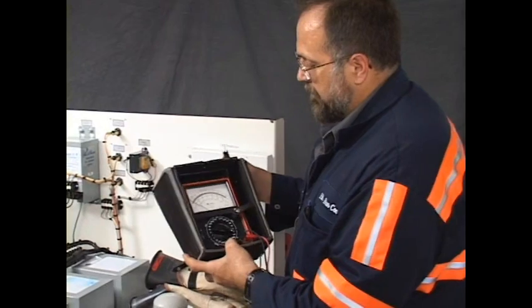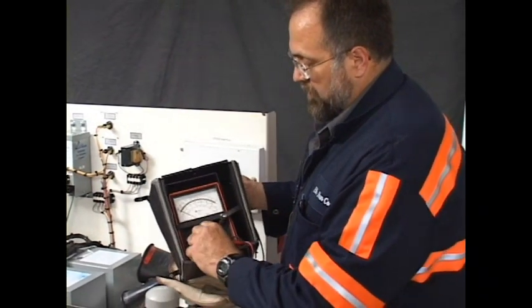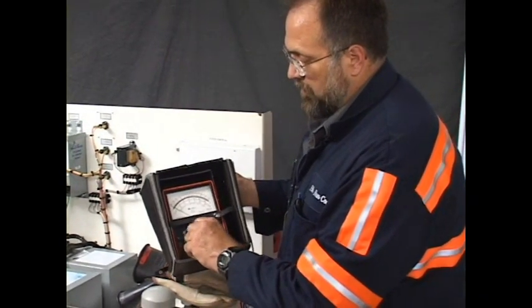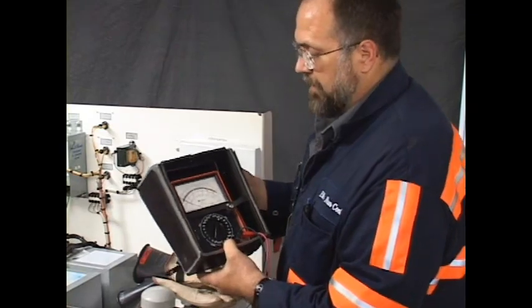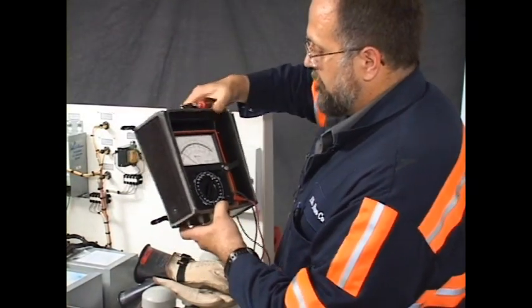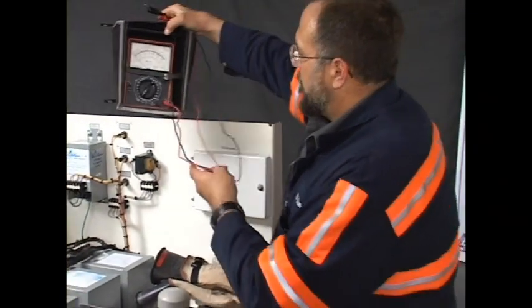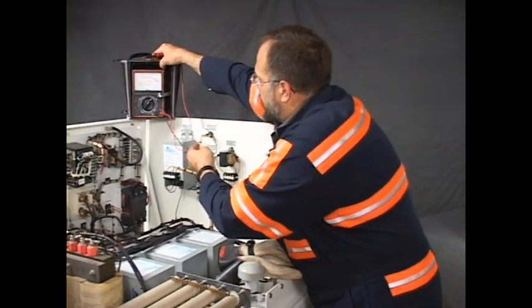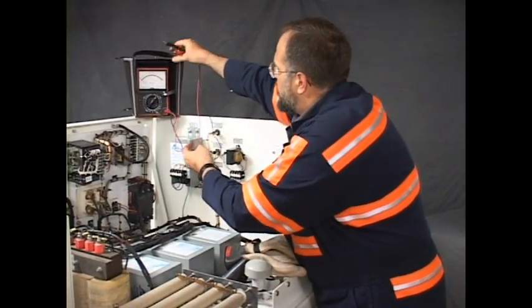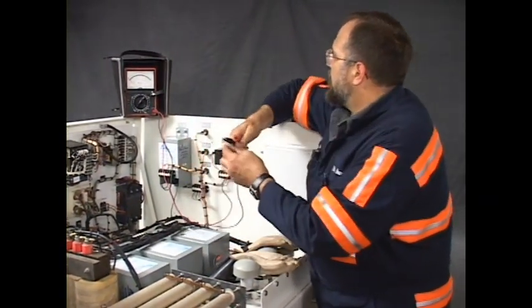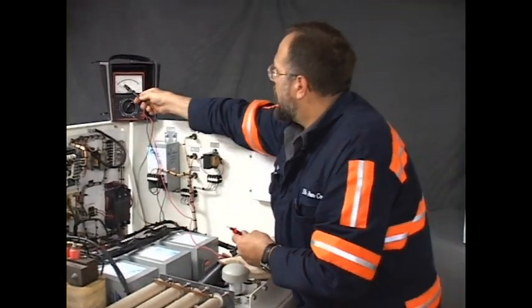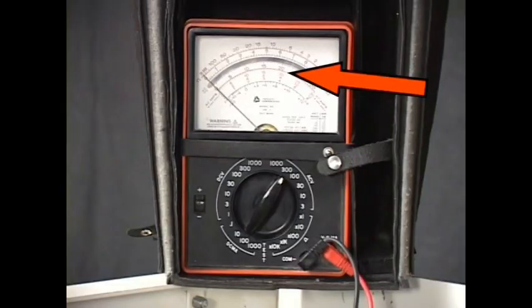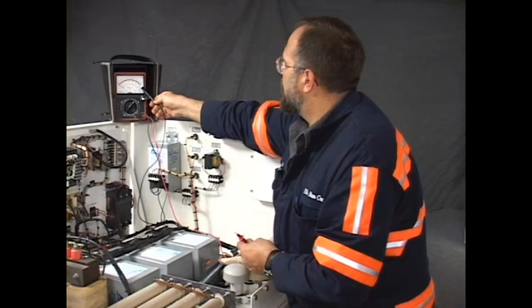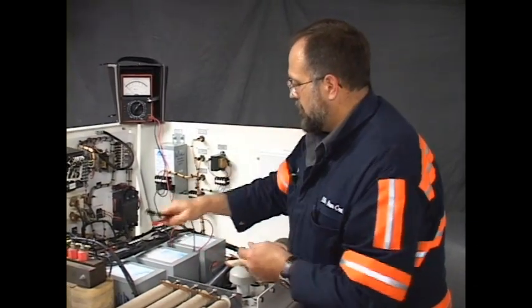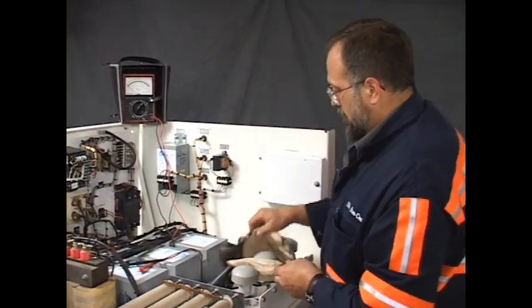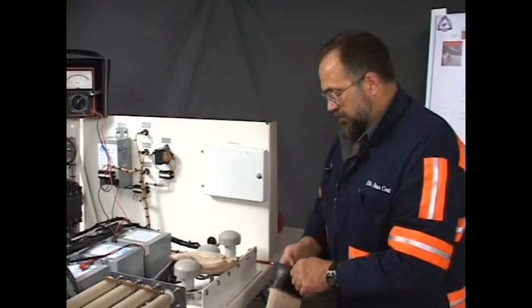I'm going to change that to read AC voltage. And I'm going to choose a scale higher than what I anticipate finding in voltage. And I've done that. We anticipate having a 120 volt control circuit. I've chosen a 300 volt scale. And it will be indicated on this line here, below the dark thick line, the next scale under. Now, I'm going to don my low and medium voltage gloves.